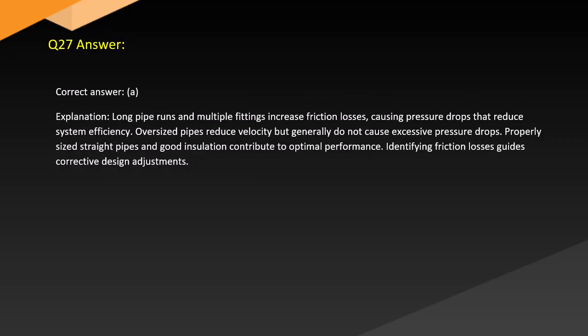Answer. Correct answer, A. Explanation. Long pipe runs and multiple fittings increase friction losses, causing pressure drops that reduce system efficiency. Oversized pipes reduce velocity but generally do not cause excessive pressure drops. Properly sized straight pipes and good insulation contribute to optimal performance. Identifying friction losses guides corrective design adjustments.